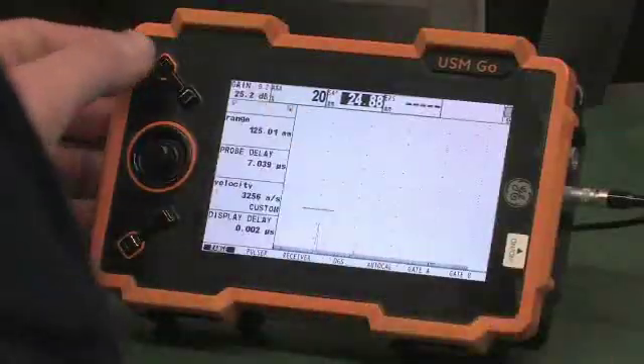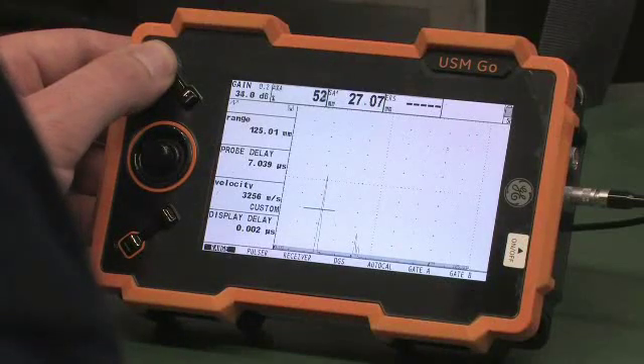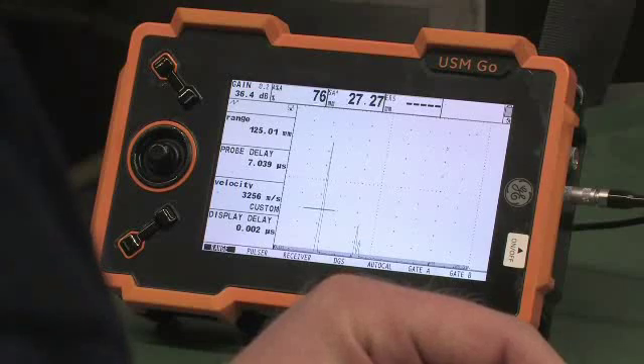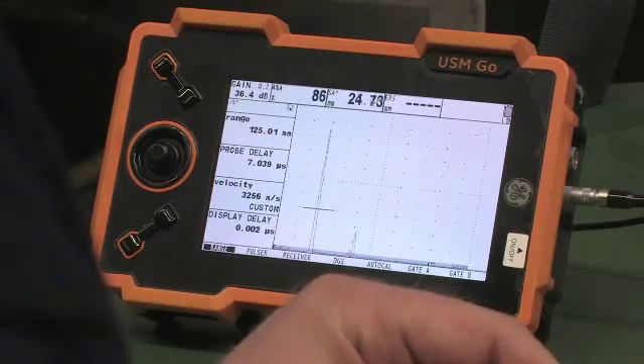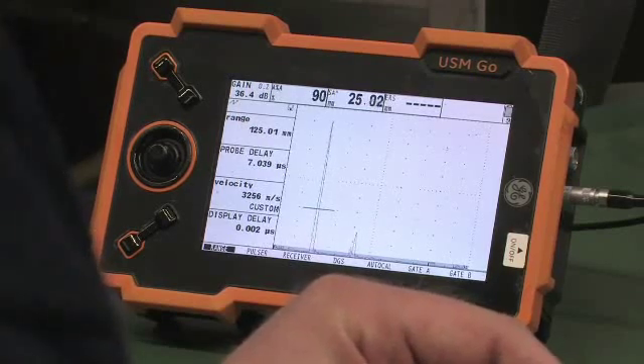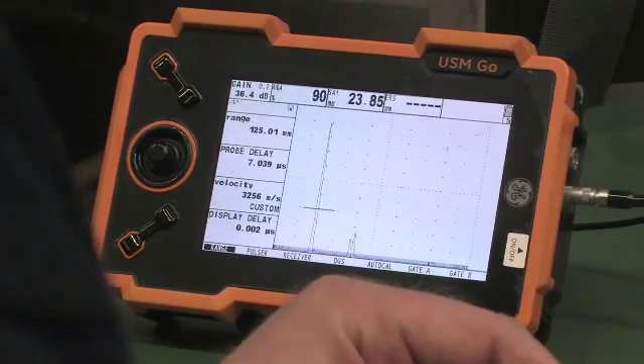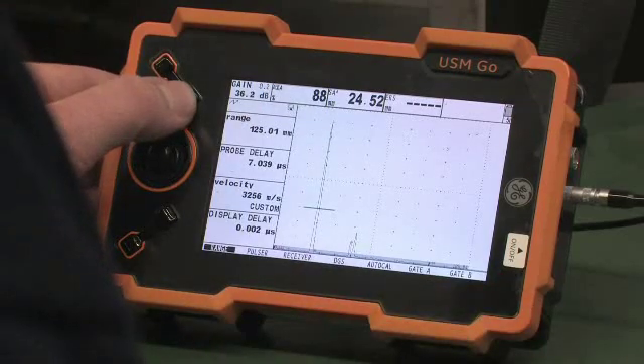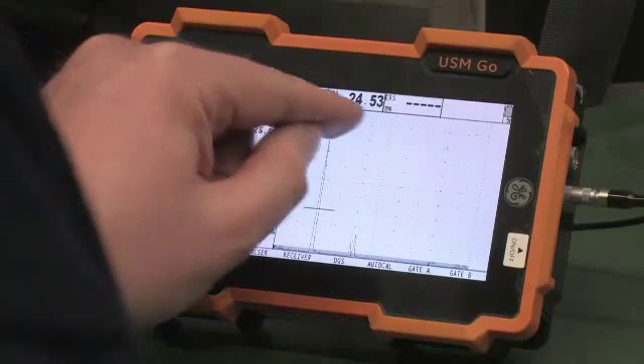Now you can size a flaw using the DGS method. First, find the flaw, position the gate, optimize the signal, then bring it to 80% screen height with the gain control. You must read and note the gain and the position of the signal: 35.4 dB and 25 mm.